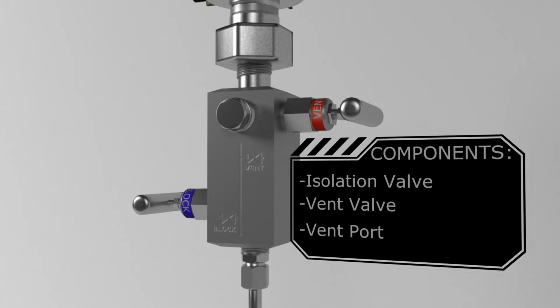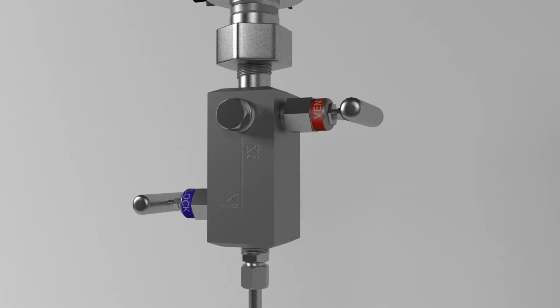There are three key components to a manifold. The isolation valve. It is used to isolate the transmitter from the process in order to perform a calibration or to service the transmitter. The vent valve. The vent valve is used to vent the remaining product in the manifold if the isolation valve is closed, or to let the air out if the transmitter needs to be blown down. The vent port. The vent port is where the product is released if the vent valve is opened. This usually has a threaded plug in it.